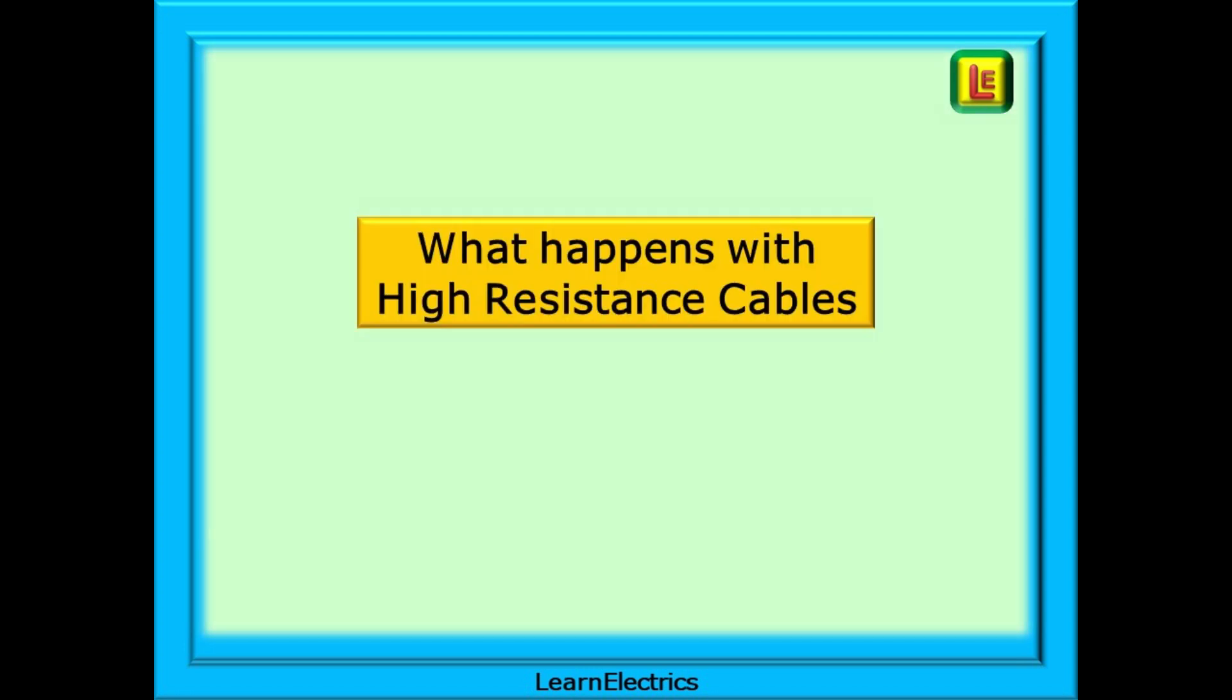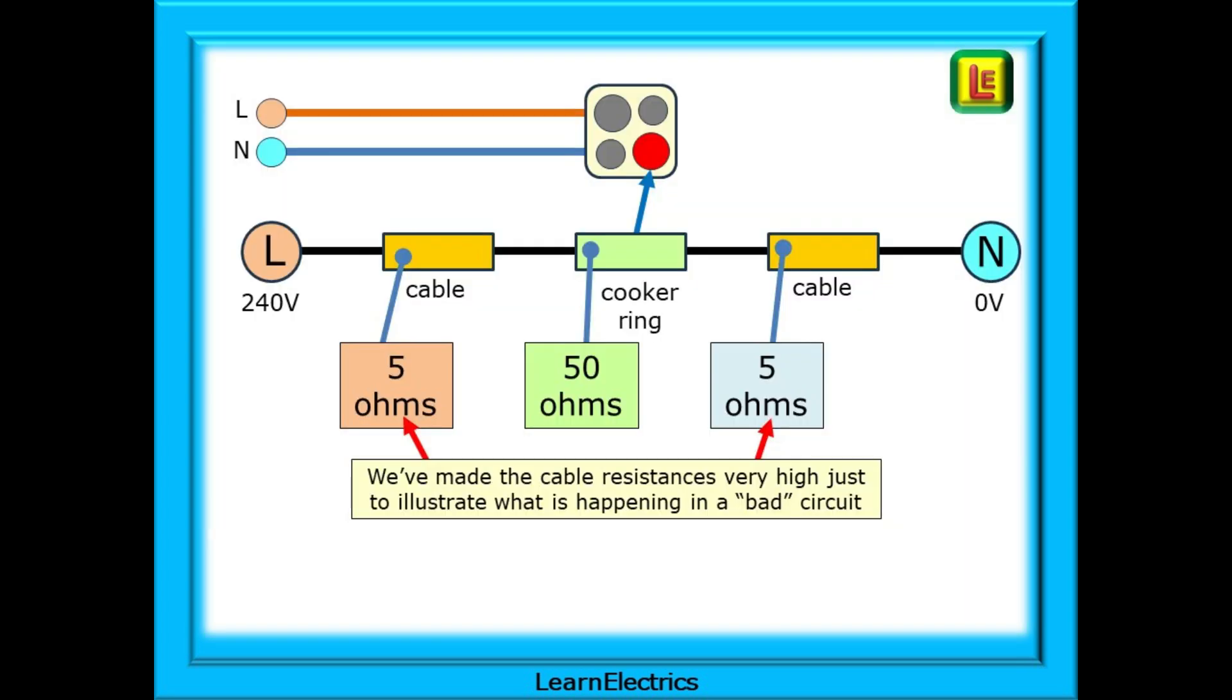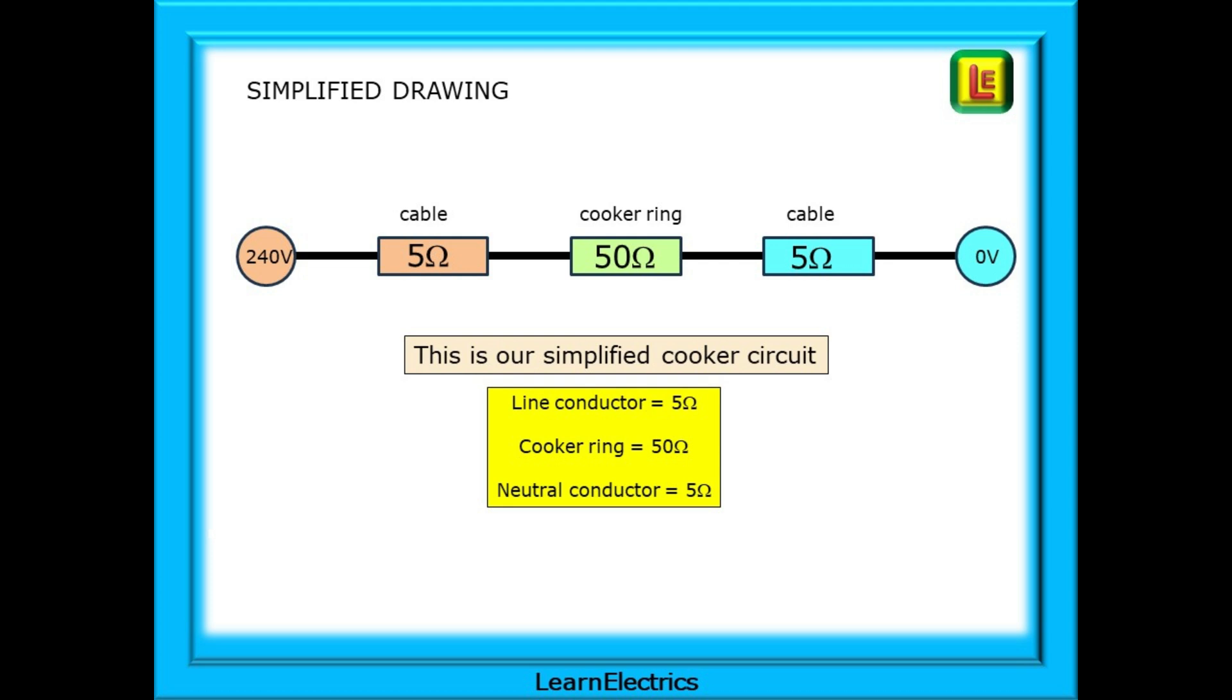Let's begin by looking at what happens in the circuit if we use high resistance cables. How does the cable resistance affect things? We've made the cable resistances very high, just to illustrate what is happening in a bad circuit. The 50 ohm cooker ring or element is connected to the consumer unit by a 5 ohm line conductor and a 5 ohm neutral conductor. Nearly 20% of the circuit resistance is in the cables. And this is our simplified cooker circuit. So let's make some basic Ohm's law calculations on it and see what happens in the circuit.